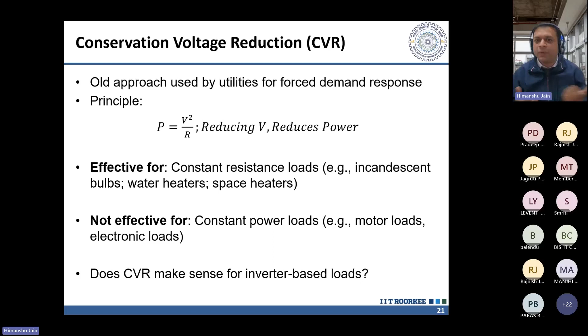And the problem for us now is that most of our loads are becoming constant power loads. Look at any modern appliance—your LED lighting, inverter air conditioners, inverter fans, BLDC fans, pumps—they are all increasingly becoming inverterized. These act like constant power loads, so the effectiveness of conservation voltage reduction goes down. But are there ways we can still use these assets and provide some power reduction? That's what we started to look at.